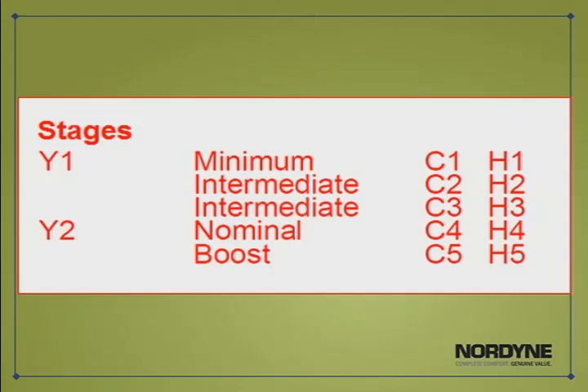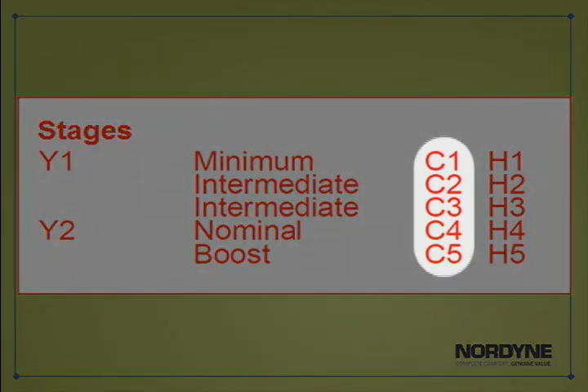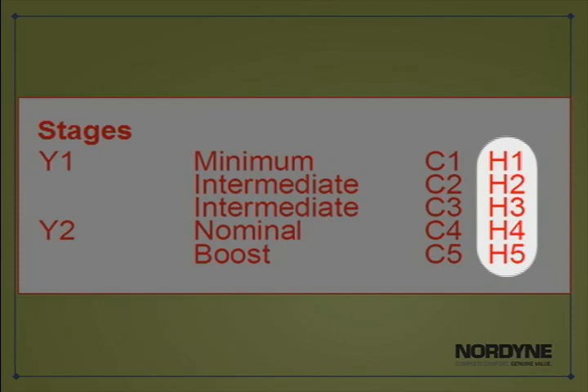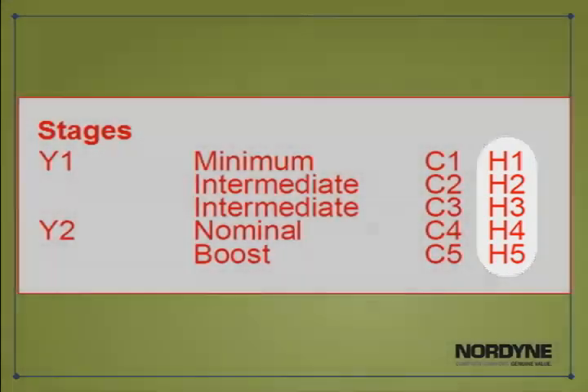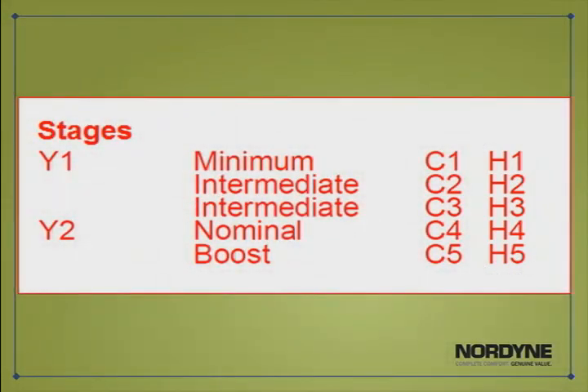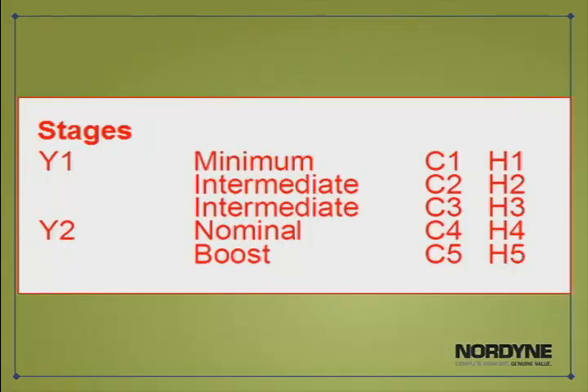Now that we've reviewed the components in the 18 SEER units, let's talk about the sequence of operation. There are 5 stages of operation in either cooling or heating modes. Cooling stages are marked C1 through C5, and heat stages are H1 through H5. When the condenser receives a call, the stage it starts at will be determined by a combination of thermostat input and length of the prior run cycle. For cooling mode, the unit receives a Y1 call from the thermostat to the interface board.